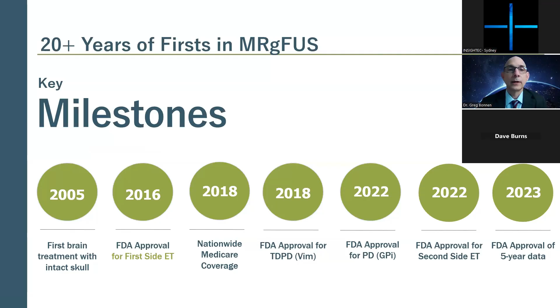So how does this actually work, or what are we doing? The patient is awake. It doesn't require sedation in any way. We do the procedure in an MRI scanner, and so it joins the technology of MRI, which allows us to look at imaging and also measure temperature with an ultrasound transducer. And this is a semicircular or kind of helmet-shaped device that has 1,024 little channels in it that will each emit a sound wave. And for any given procedure, we usually have somewhere between 950 and 1,000 of these little elements or channels on.